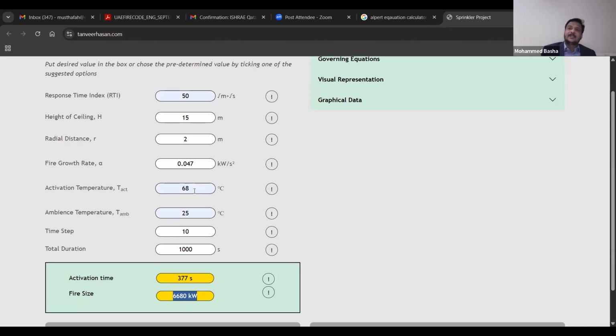So if the ceiling height is getting increased, the velocity of the water coming from the top will be disturbed at the bottom before it reaches the fire plume. So I would say at least 4 sprinklers around the fire should be activated. Then I will freeze my HRR. This is the concept. This is a very conservative approach, because 4 sprinklers around the fire is well enough to control the fires. Okay, now let's see some simulations again.